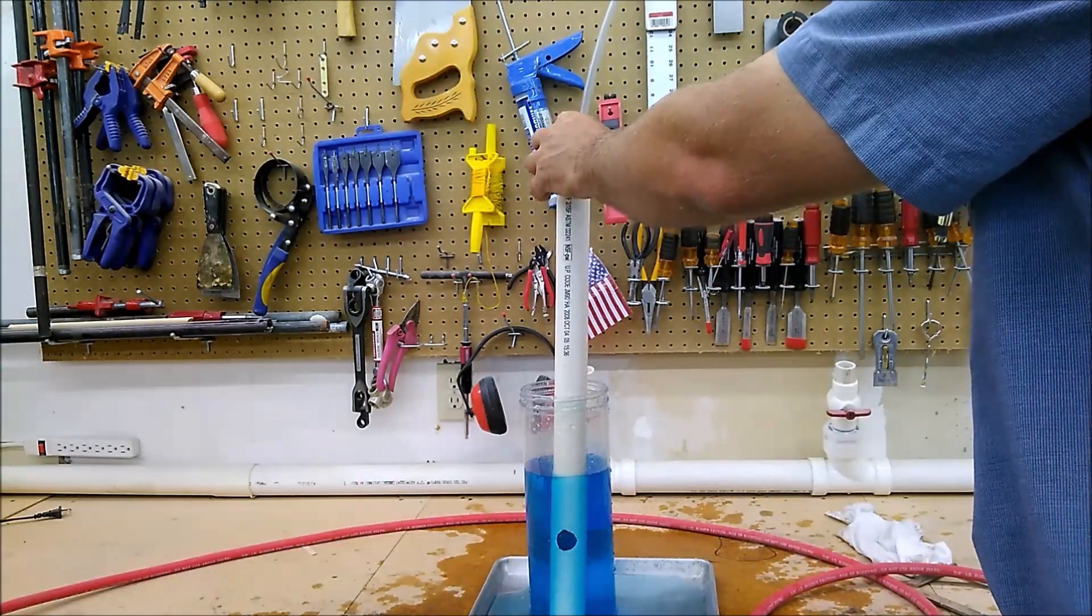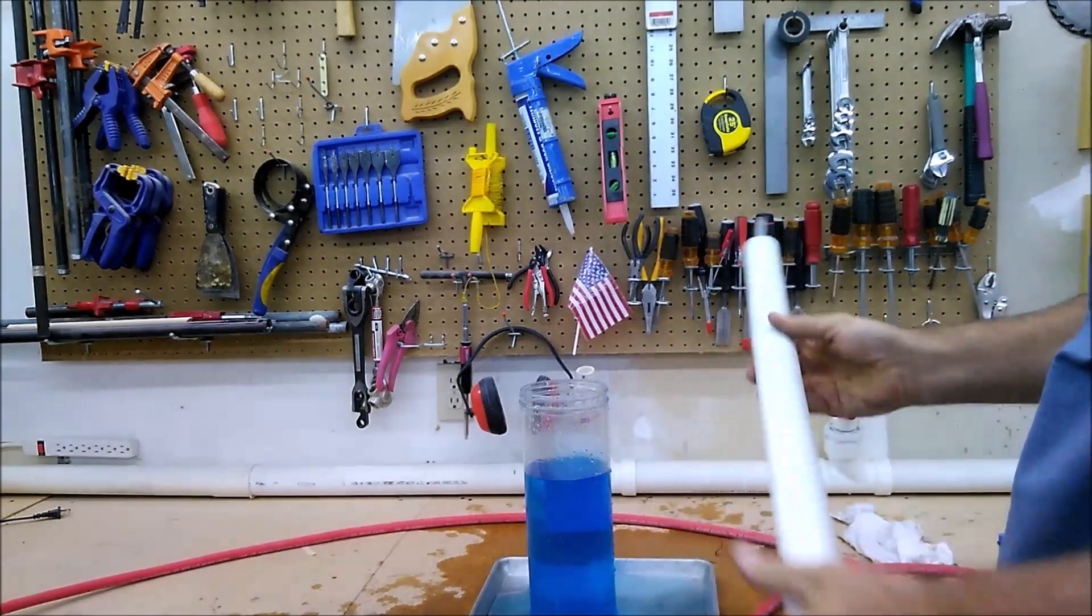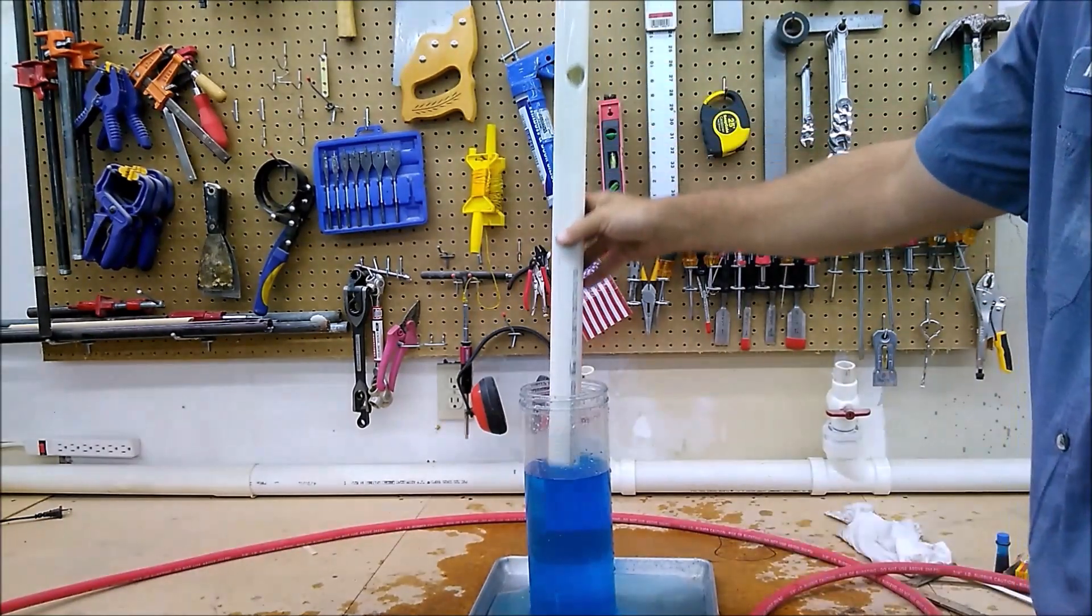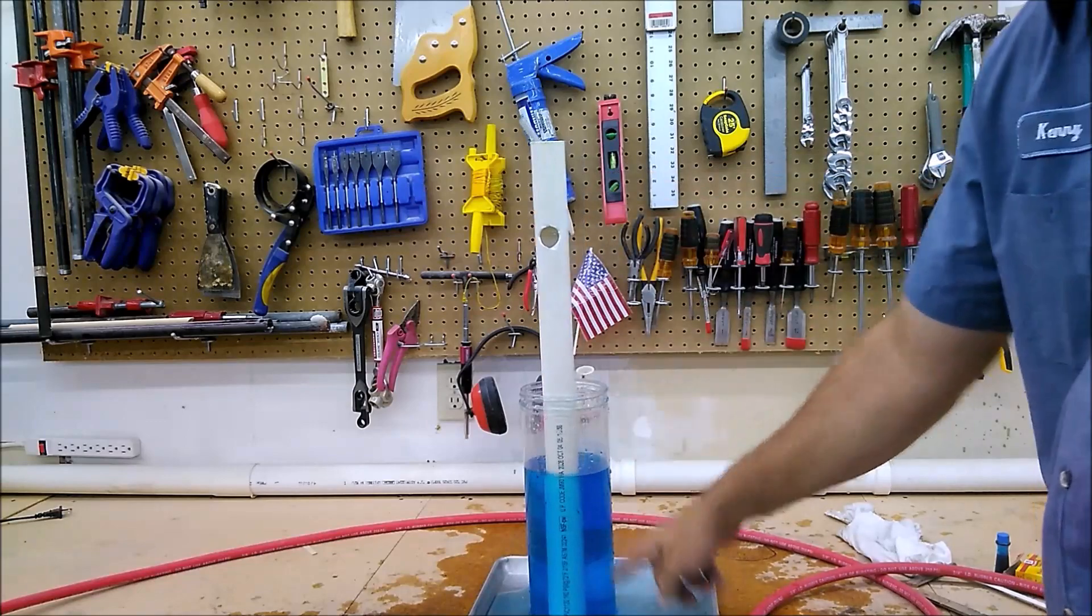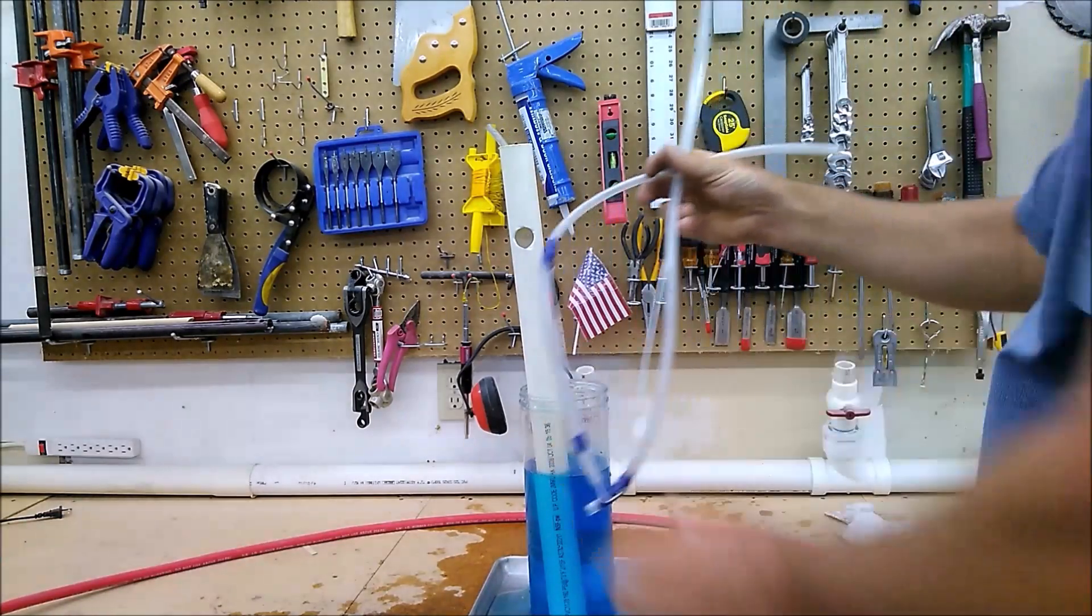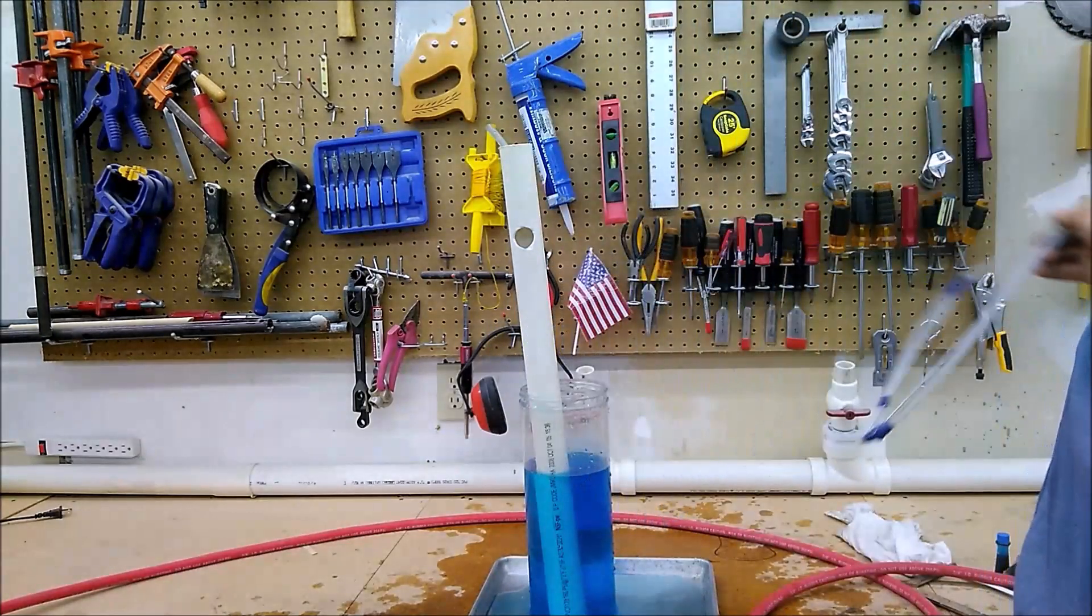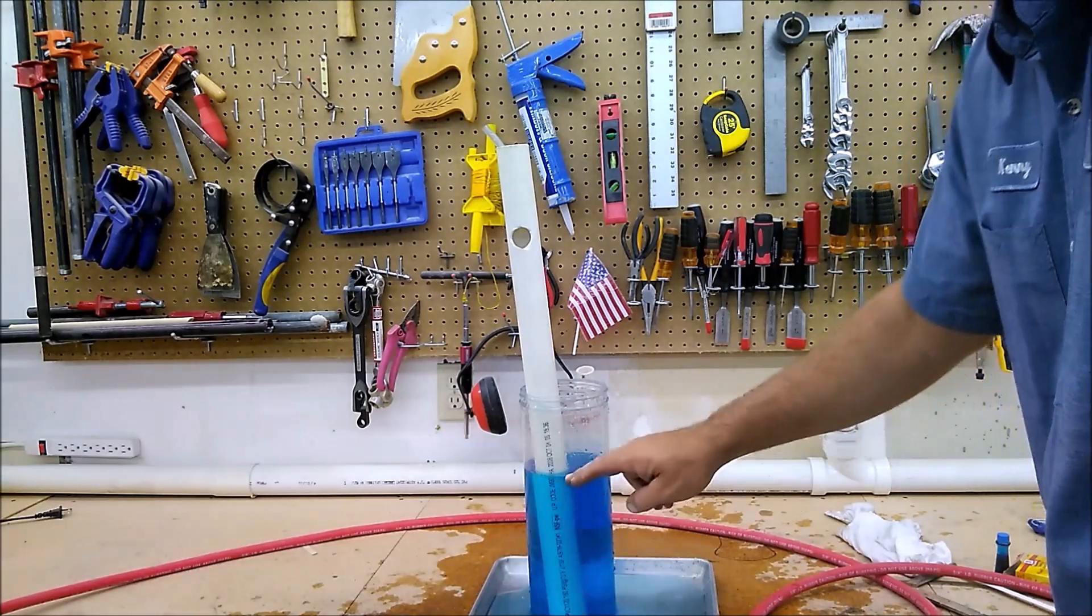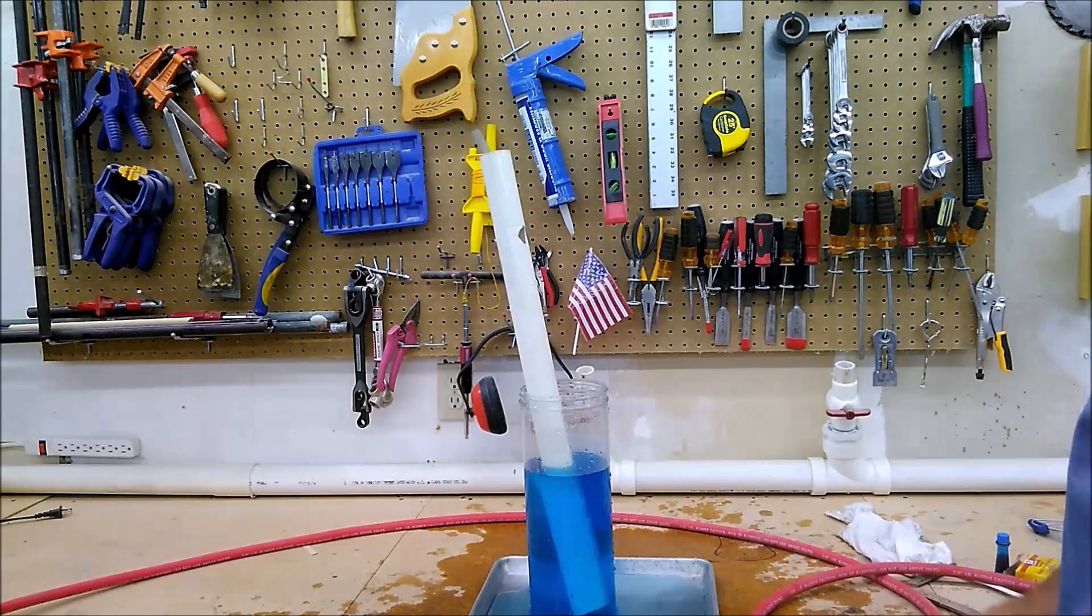One solution to that, if we consider this to be our casing again, is to run a second line all the way to the bottom. And you're essentially making a two-pipe system just like this one, only you're doing it with one pipe inside of the other. Then your total head available is clear to the bottom of the hole instead of being up where your perforations are.